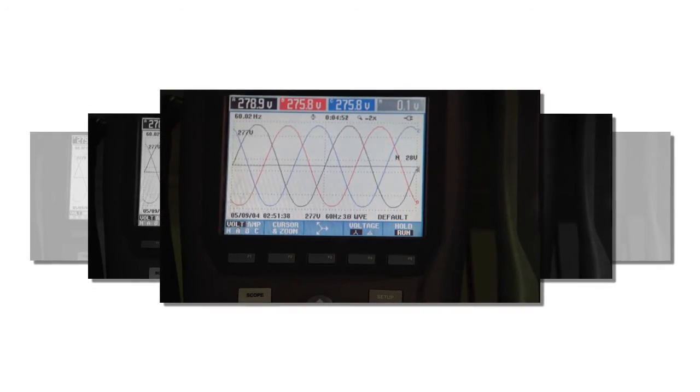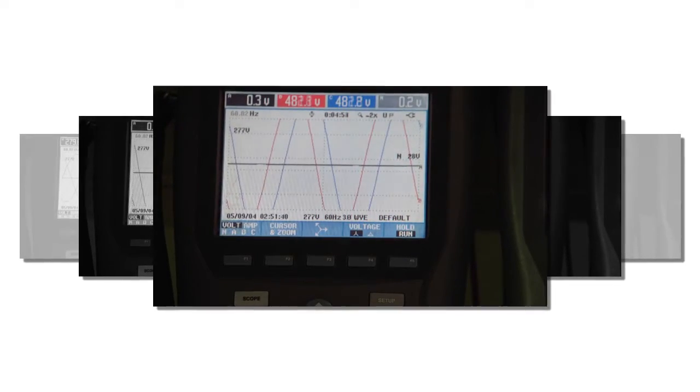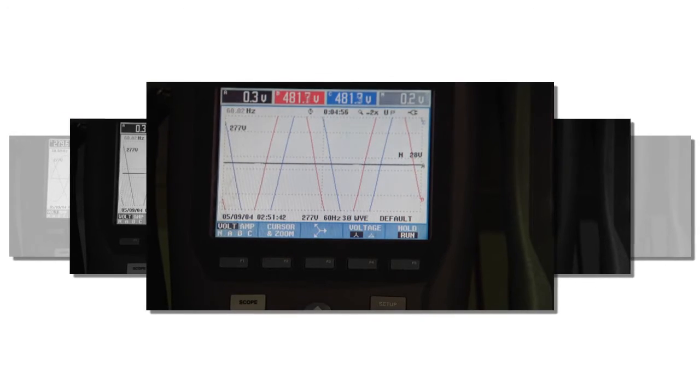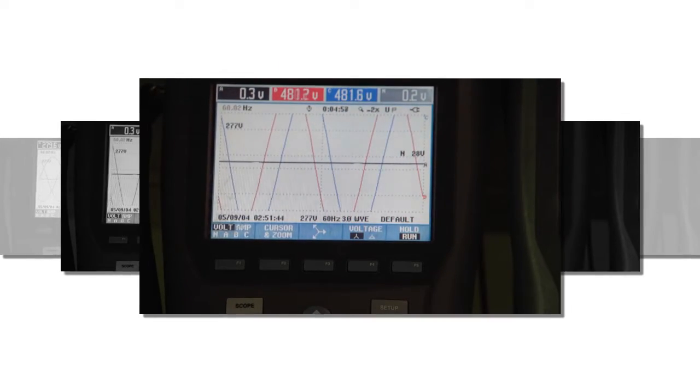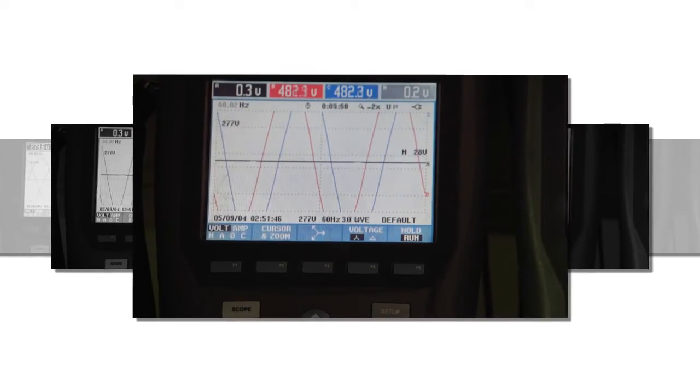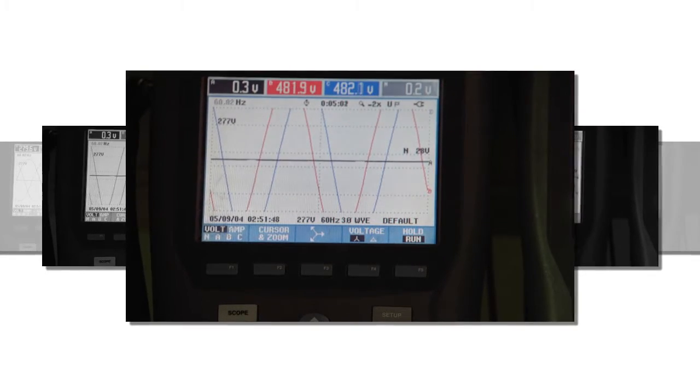During a ground fault condition, when phase A, for example, goes to ground, the other two phases go to the line-to-line voltage, in this case 480 volts. So it's like a corner-grounded delta system.